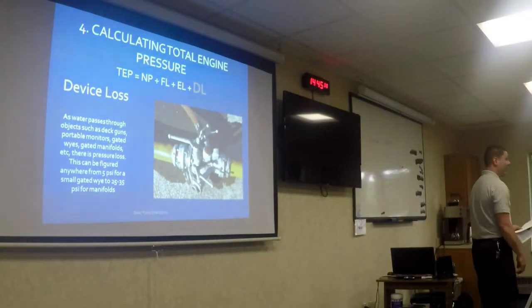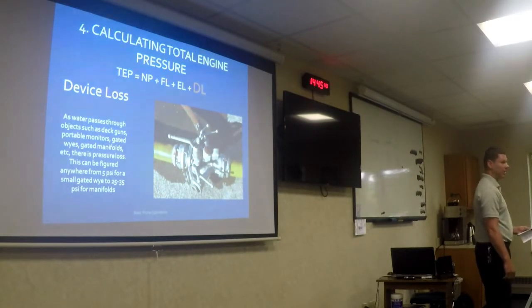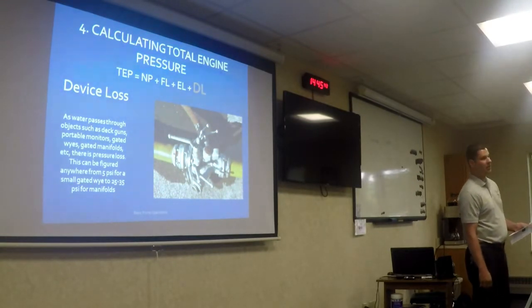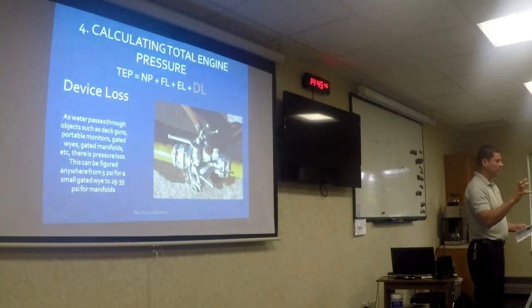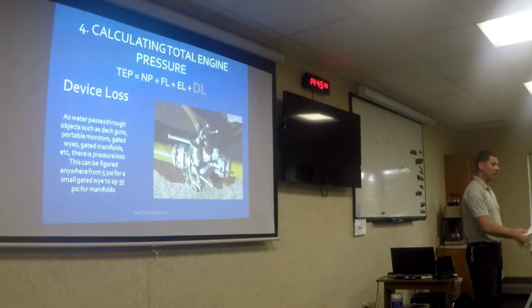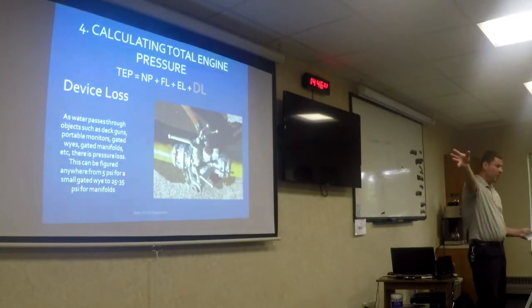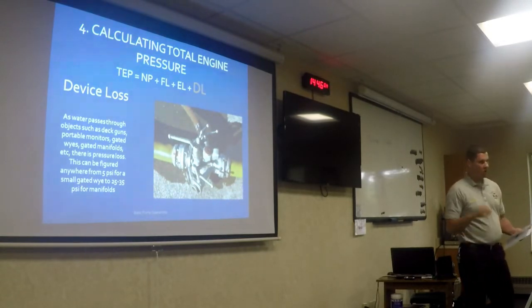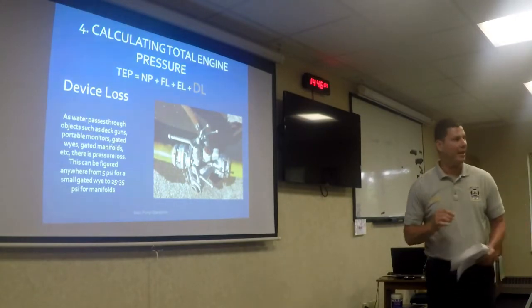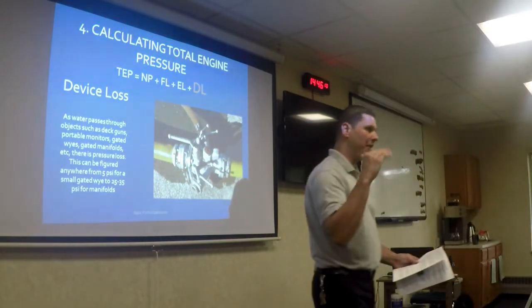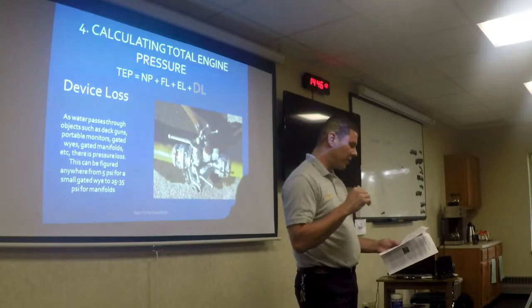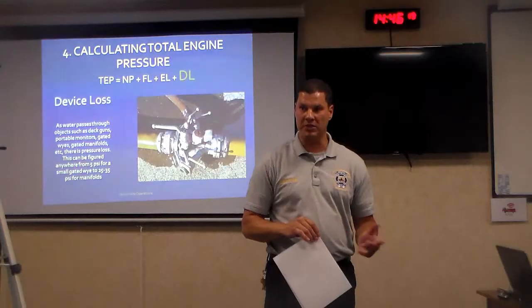Okay? I went over to 31 to just kind of follow the pathway of water. Every time there's a bend in that system, that's where the device loss kicks in. And there's quite a bit of it. There's quite a few bends. I want to say I counted a dozen different bends from the time the water gets from the platform up to where it gets to the bucket. So these are key numbers that we probably have not been adding to our friction losses when it comes to elevation for master streams. 25 psi for up to 1,000, more than 1,000, 50 psi. There's a lot of friction loss, but that's needed in order to get the flow rates that we need. Okay?